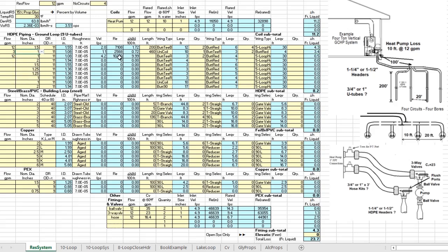Okay, and you might get kind of worried that this is going into laminar flow, but see, there's a number right there, 2568. That's in transition, so we're good to go. So we're down to 23.7, which we could get with one pump, and I can assure you that pump's going to cost $500 or $600, and the cost of switching from the 3/4-inch to the 1-inch U-tubes and to the 1.5-inch headers is much less than $600. Okay, and we've improved the efficiency by about 10%.